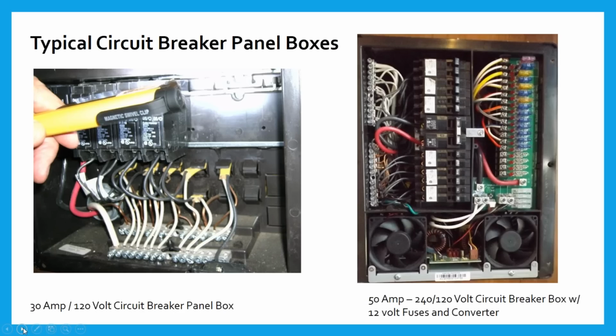Notice how the white wires and bare copper ground wires are kept totally separate from each other. In this circuit breaker panel box, the big heavy white wire is part of the power cord. Look at the red wire going into a circuit breaker, the black wire going into a circuit breaker, and then there's a heavy ground wire. So what we've done is bring these wires in and terminate them.